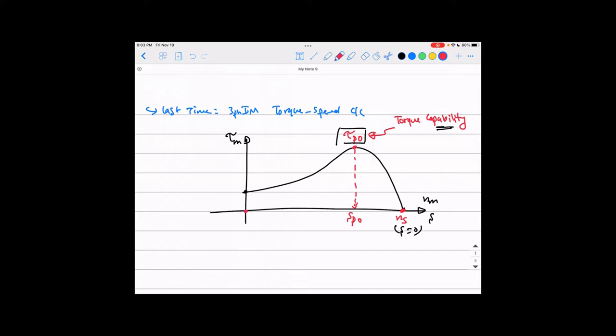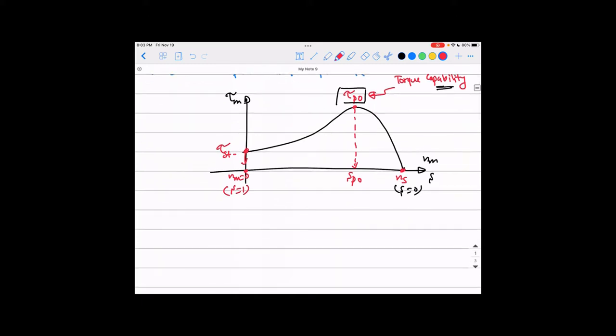At synchronous speed the slip equals zero. At the other end where mechanical speed equals zero, that is the beginning of the curve, the slip equals one. This point represents the starting torque — the torque the motor is capable of producing at zero speed. That is a very important value for any motor, because at starting the motor torque must equal the load torque plus the friction torque B·ω plus the acceleration torque J·dω/dt.